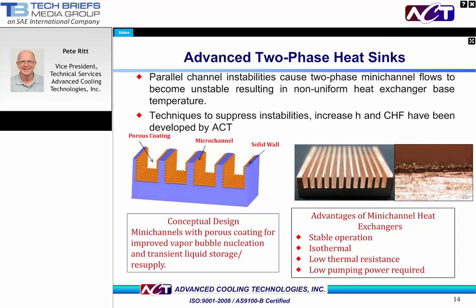The addition of the microporous coating adds numerous potential nucleation sites across the evaporator where bubbling can occur. This improves the likelihood of bubble formation throughout the evaporator, improving temperature uniformity. The microporous particles also absorb some of the working fluid, decreasing the probability of dry out. The advantages of this solution are listed on the lower right. It offers stable operation with minimal instabilities, good isothermal performance, low thermal resistance, and low pumping power. Above that is a sample microchannel cooler with a close-up of the microporous coating on the right. This solution can be applied to any of the applications we described previously. Let's now look at some results.